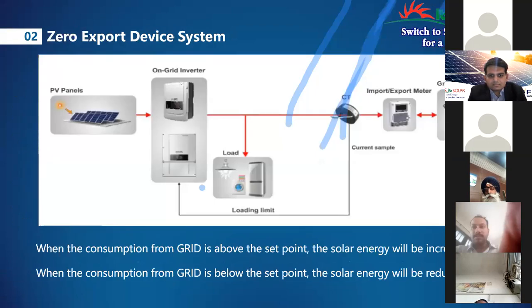Based on this feedback from the CT device, the inverter changes its maximum power point to regulate the generation. In this diagram, you can see the connection of the CT, connected via cable to the inverter, giving feedback of the load current, which is continuously regulating. So the CT senses the load current and gives feedback to the inverter.